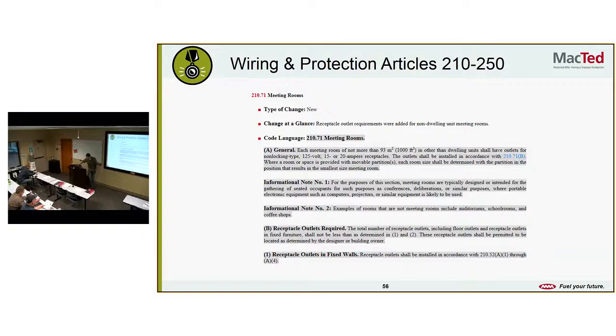So, looks like each meeting room of not more than 1,000 feet. So, if you're under 1,000 square feet, then you need to have at least a 125 volt, 15 or 20 amp receptacle. Somebody must have been trying to get away with making small meeting rooms without outlets in them, calling them meeting rooms. Now they're saying if you're gonna have a meeting room, you gotta have power to it. Yeah, they don't want you running cords underneath the partition walls to run an overhead projector or something like that. That makes perfect sense. More power is better.